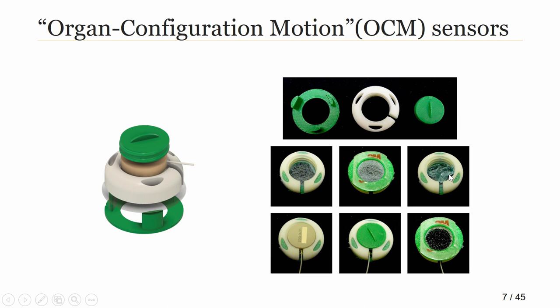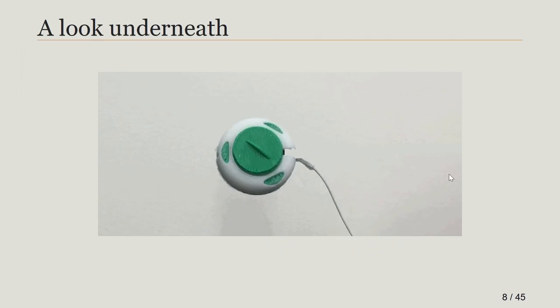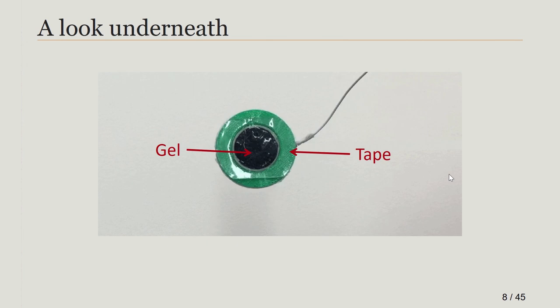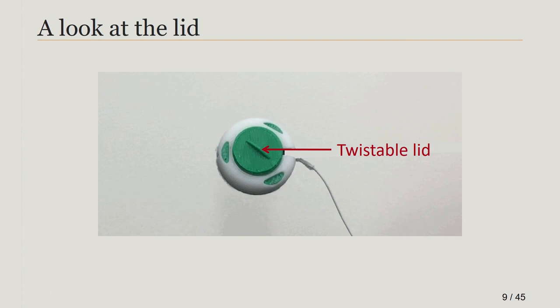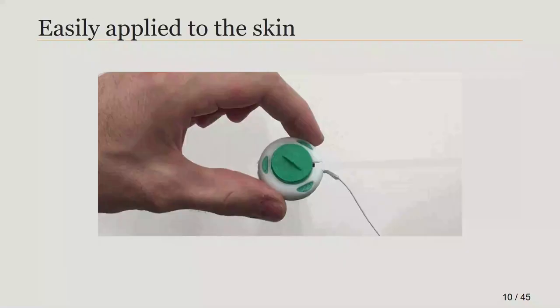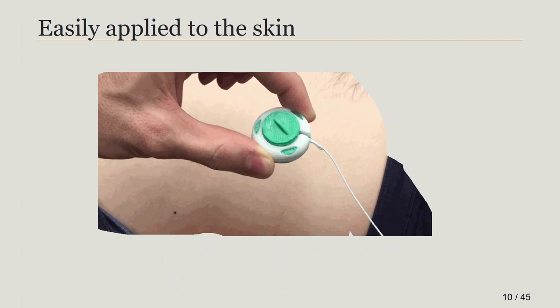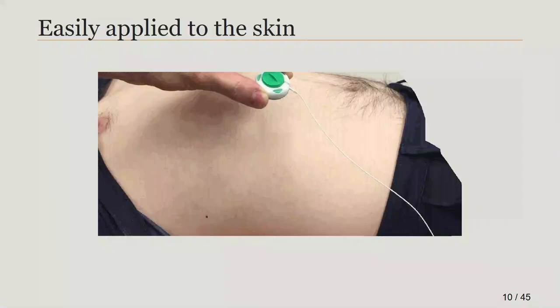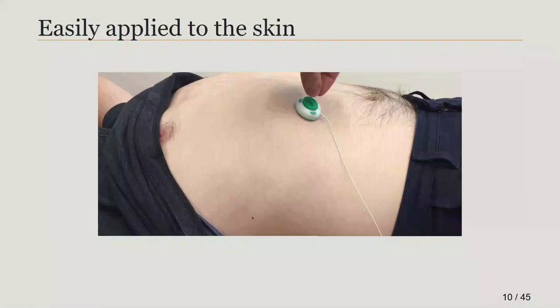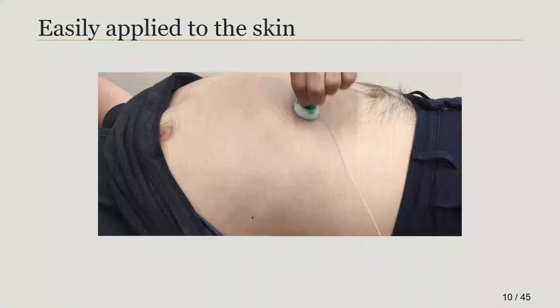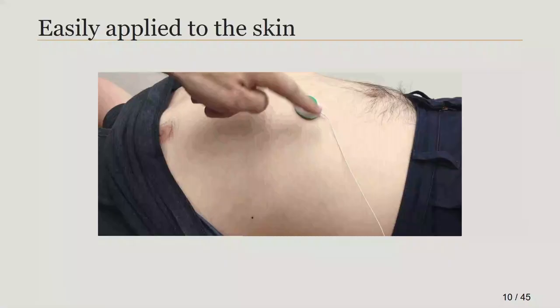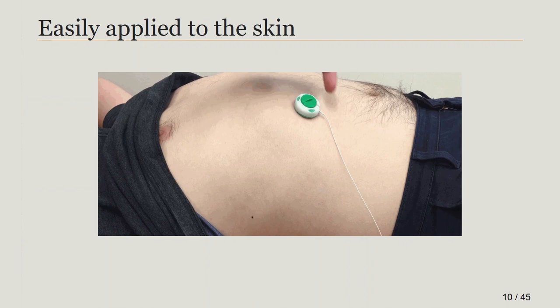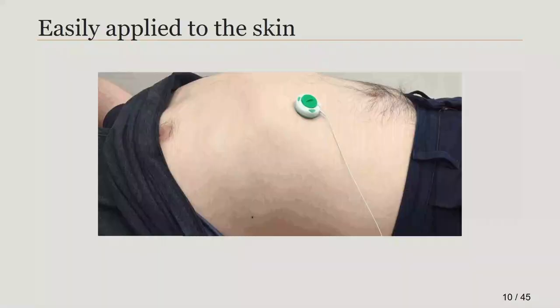The capsule includes a special membrane that is substantial enough to contain the ultrasound gel, yet porous enough to let the gel through once pressure is applied. Looking underneath, there is a tip for alignment, and you can see the actual sensor through the gel and through the membrane. On top there is a twistable lid, and applying it to the skin is quite easy. Once pressed onto the skin and the lid is twisted, it pushes the transducer downward toward the skin for better acoustic coupling, and it sticks to the skin reasonably solidly.